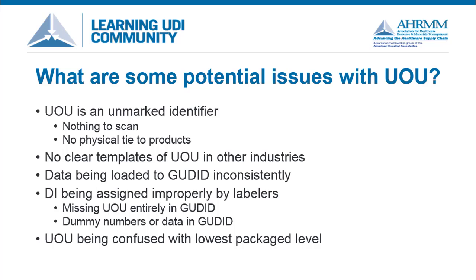The novel nature of this concept has resulted in confusion regarding the creation and implementation of the Unit of Use Identifier. As an unmarked identifier, there is no physical barcode to scan. In order to use the UOU DI, it may be necessary to create alternative mechanisms, such as using shelf tags or reference labels on storage bins to represent the Unit of Use DI. Additionally, some manufacturers may have loaded data to the GUDID inconsistently. The Unit of Use DI may be missing entirely or contain dummy numbers and/or data. We also have examples where the Unit of Use DI is confused with the lowest packaged level.